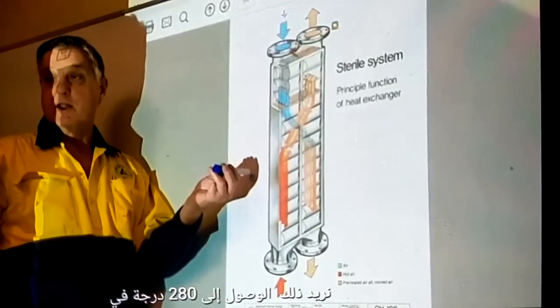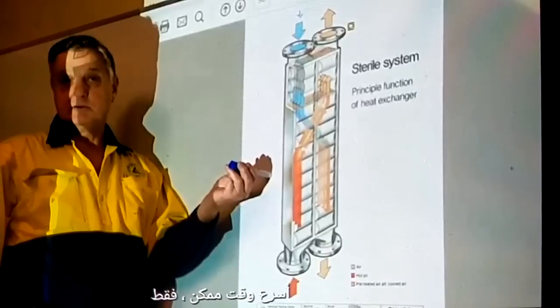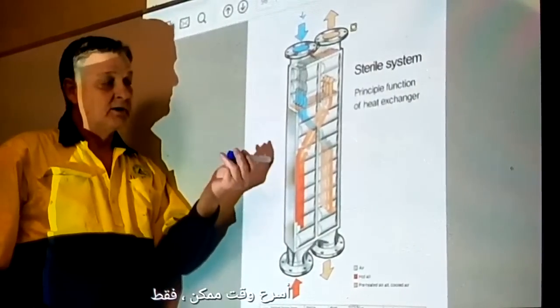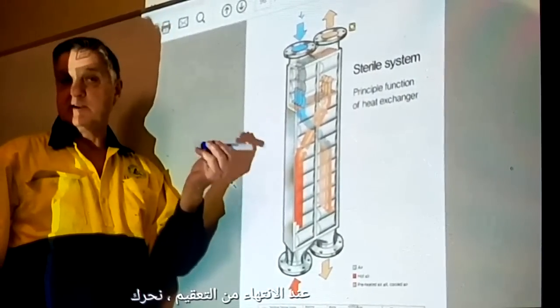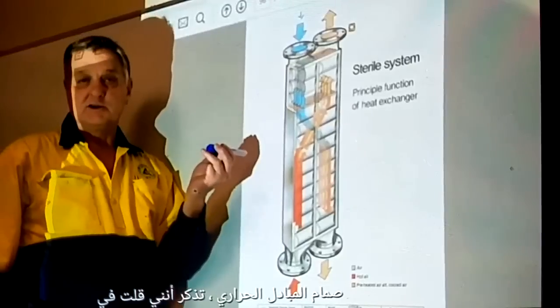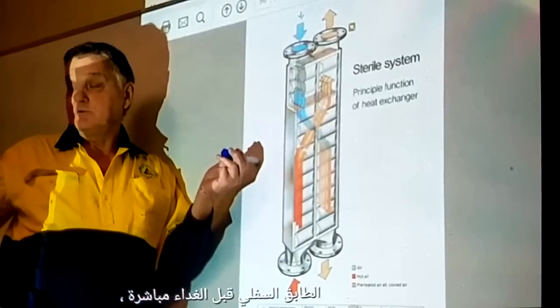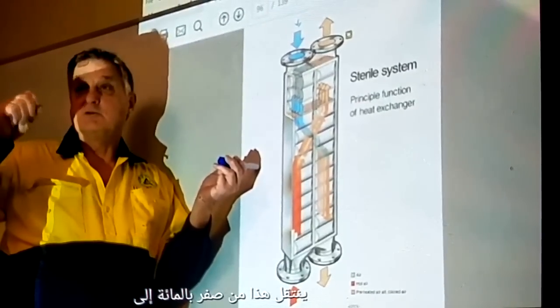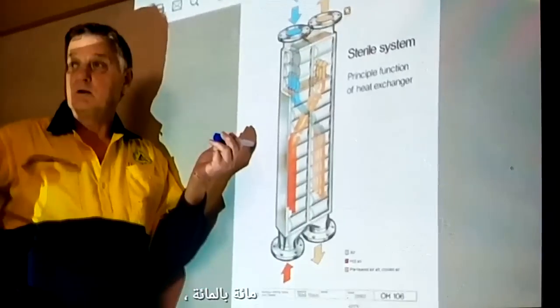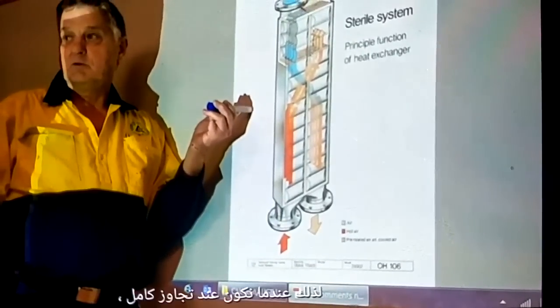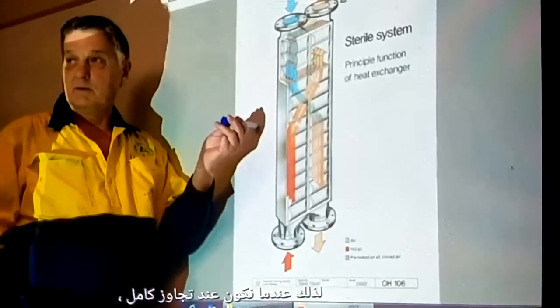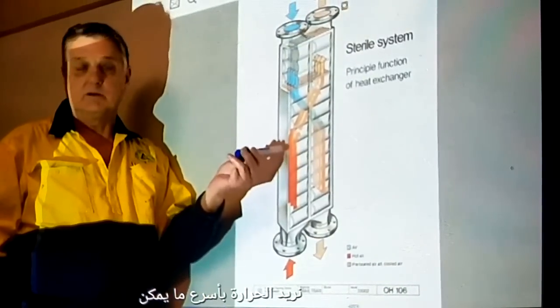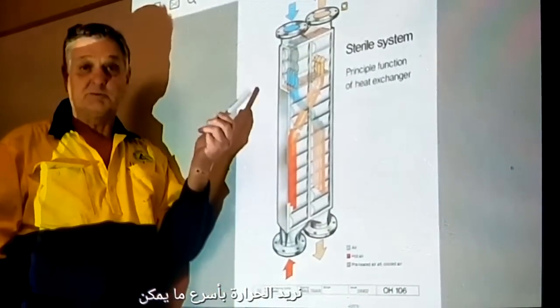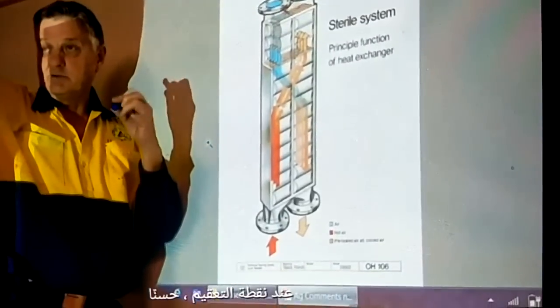We want to reach 280 degrees, as you say there. It's only when sterilization is finished that we move the heat exchanger valve. Remember I said downstairs just before lunch, it goes from 0% to 100%. So when we are at full bypass, we want heat as quick as possible at the sterilization point.